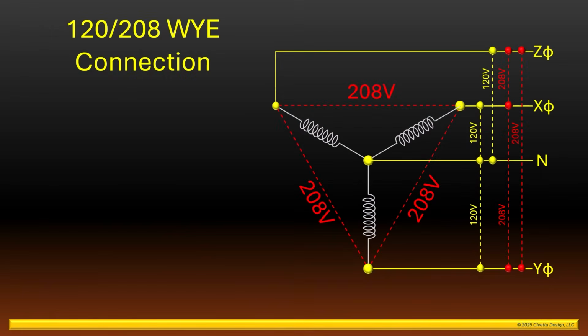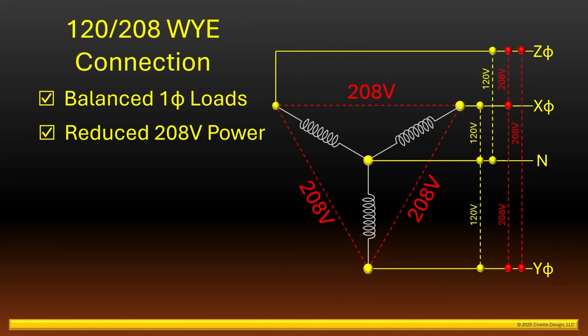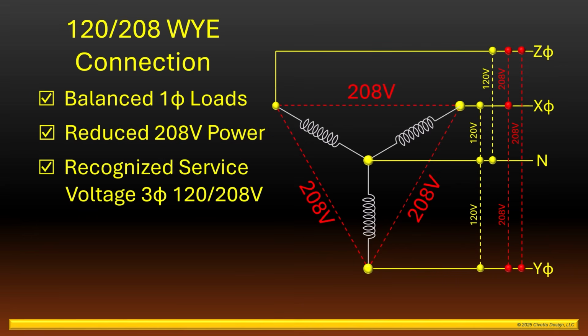A couple quick things to mention before we conclude. The Y-connected 120/208-volt transformer bank is able to provide balanced 120-volt single-phase power across all three transformer windings. However, the three-phase power output is reduced from 240 volts to 208 volts.